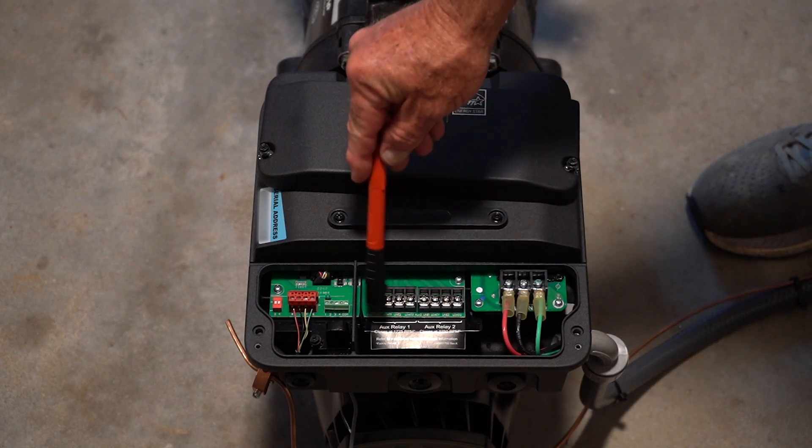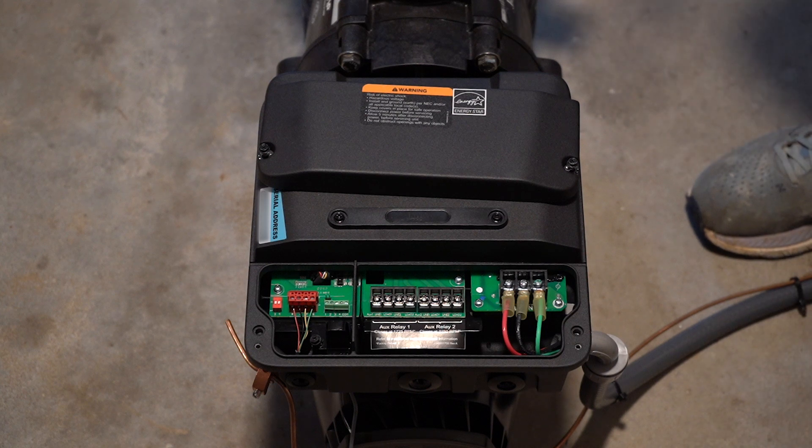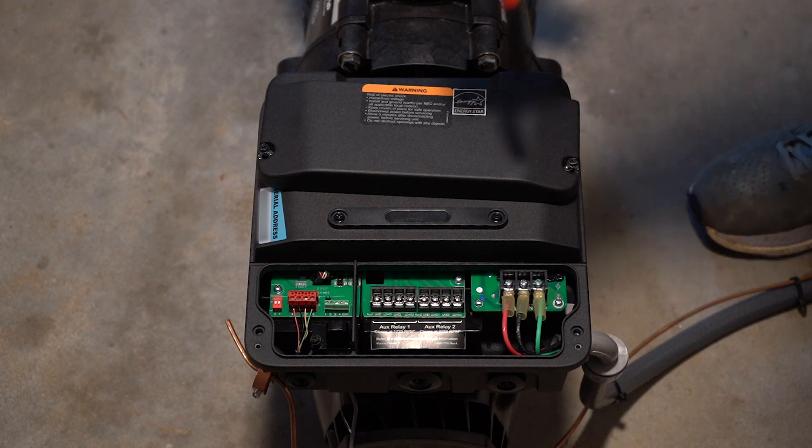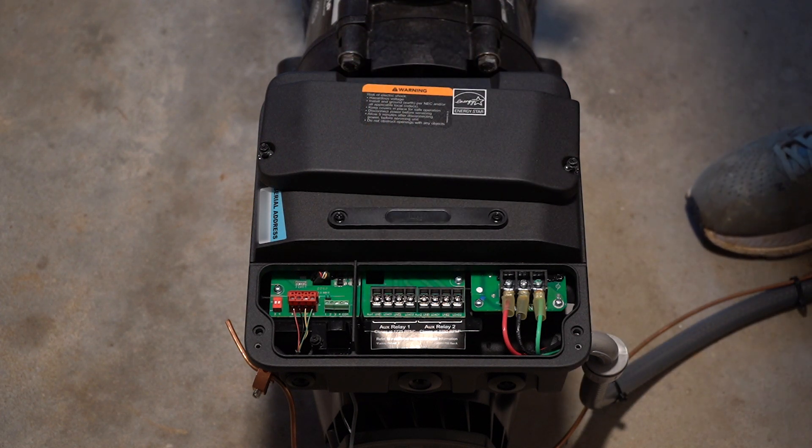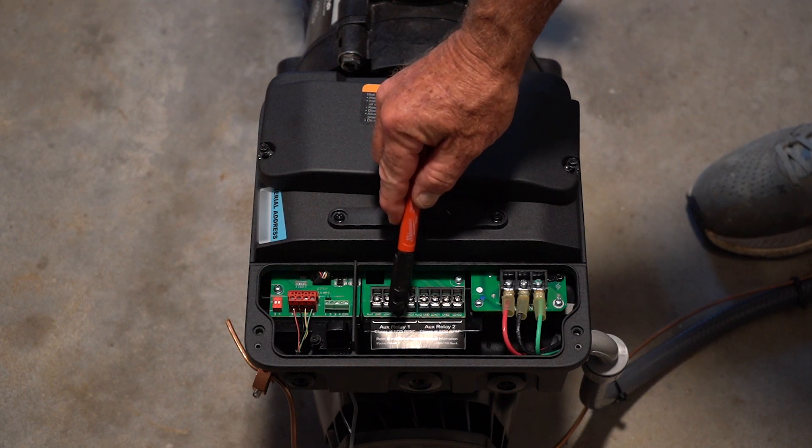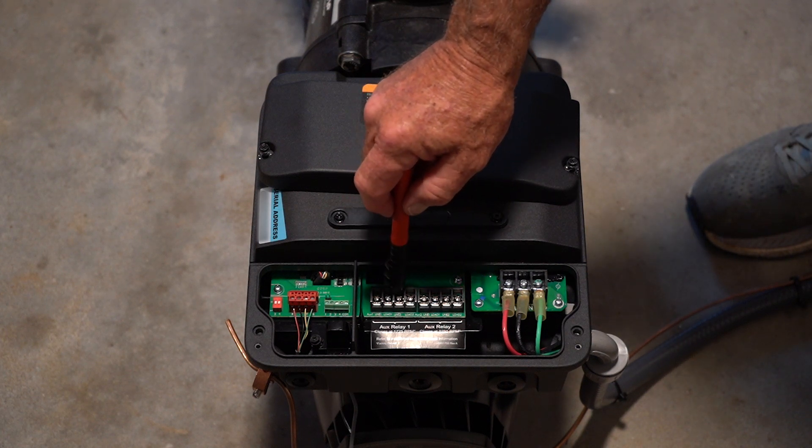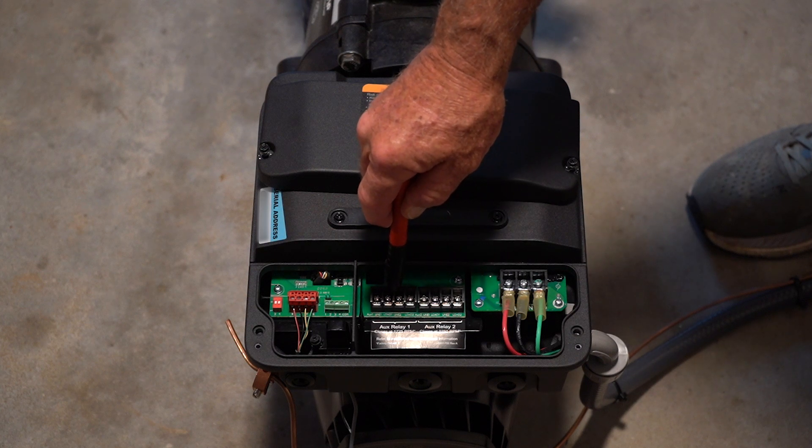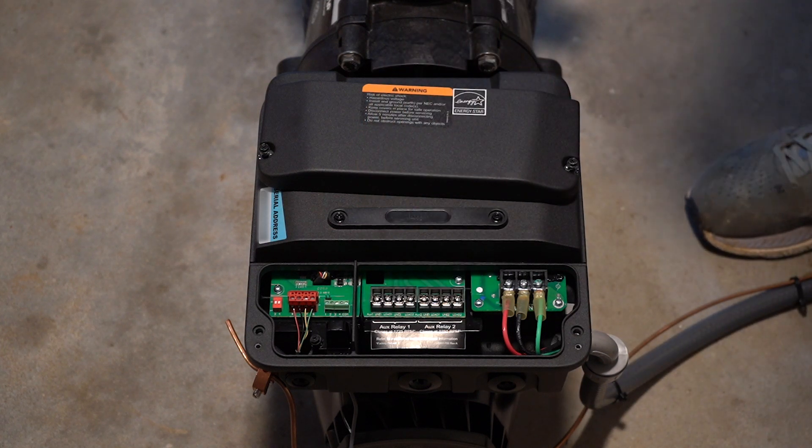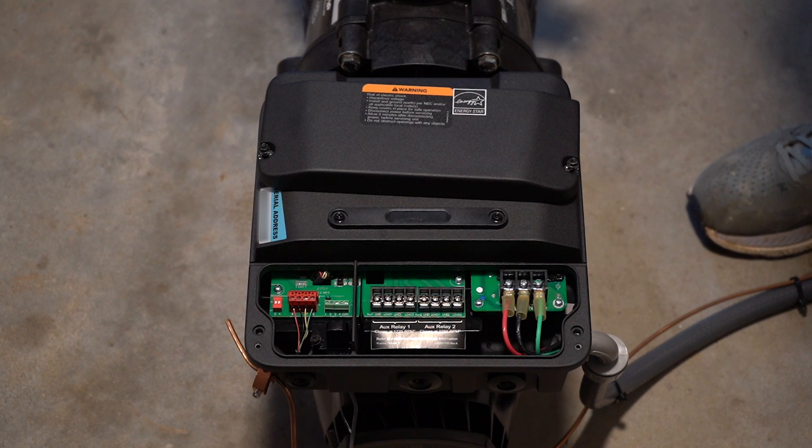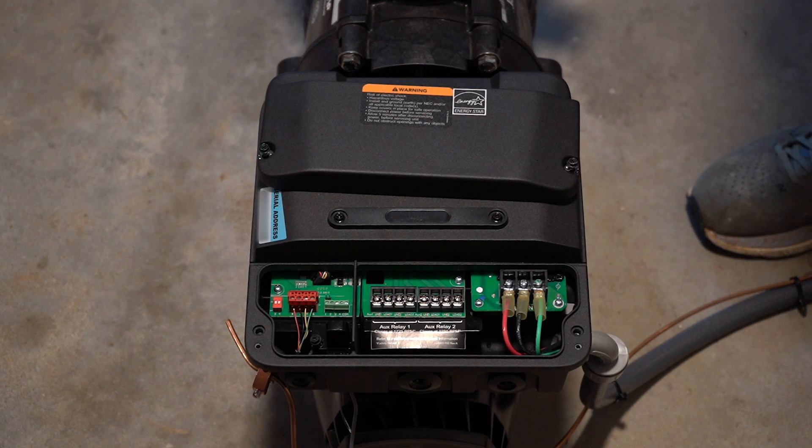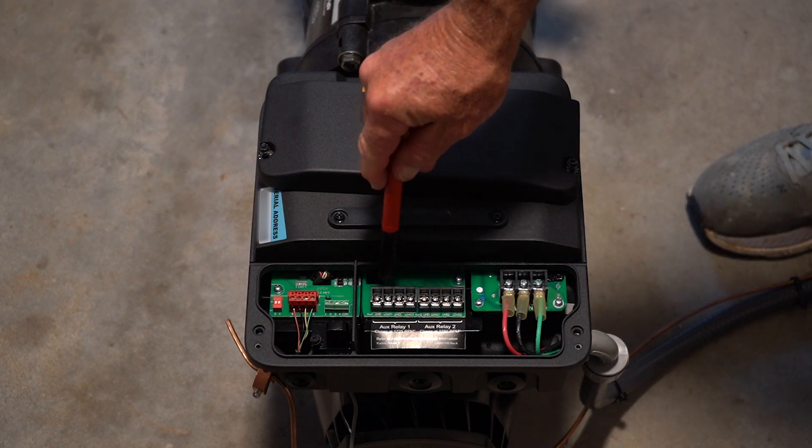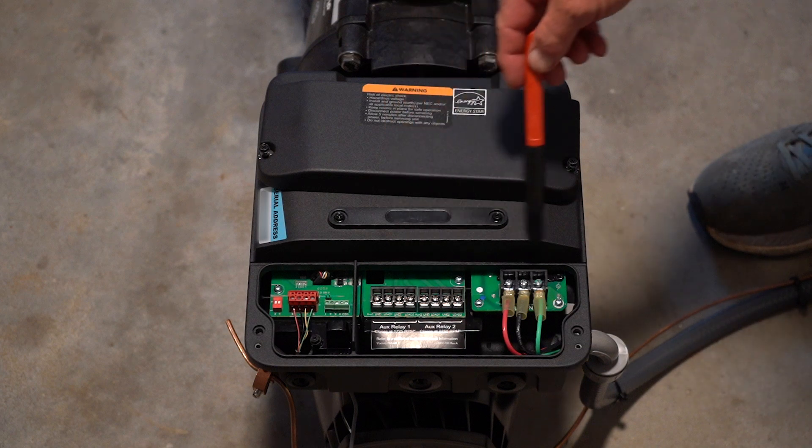And now you have two sets of relays. People ask, what is the purpose of those relays? Well, relay number one engages when you get up to 1725 RPMs. So this would actually turn on the circuit to your salt system because that needs to have about 25 gallons a minute to work correctly. Technically there are codes that require it to be turned off when you don't have enough flow and especially if there's no power to the pump. So you can use this to actually turn on your salt system.